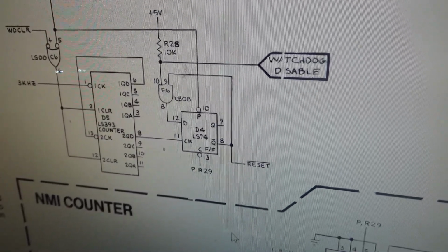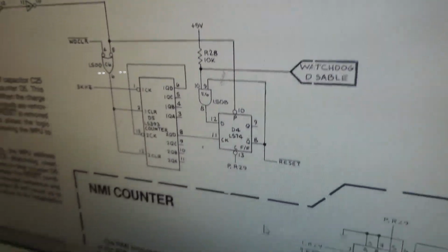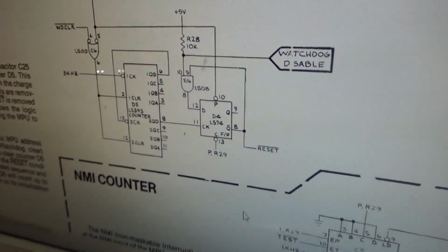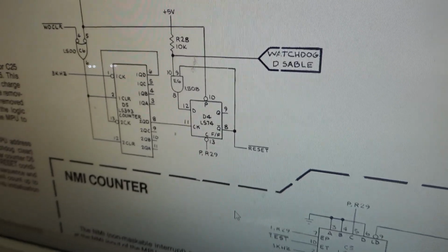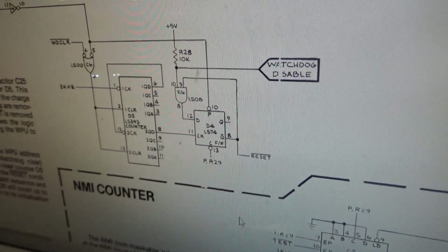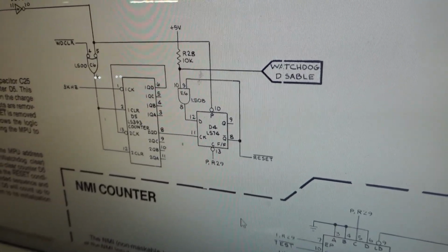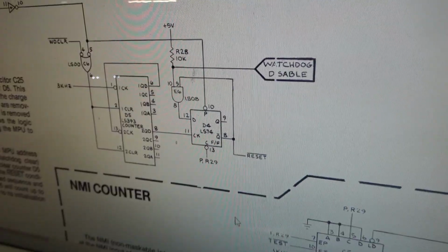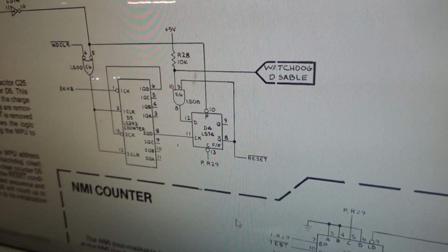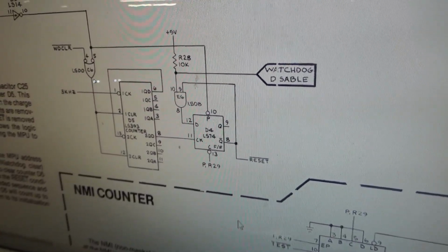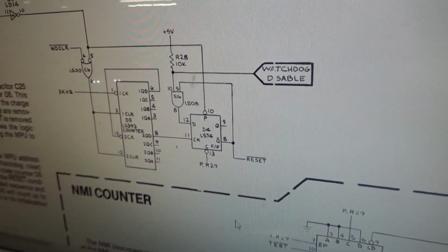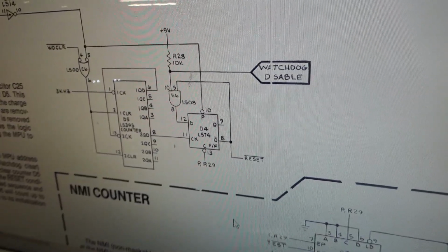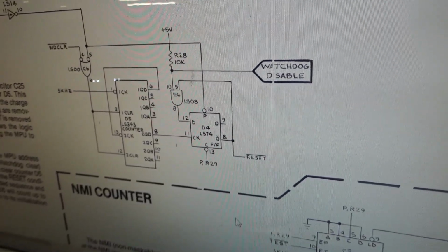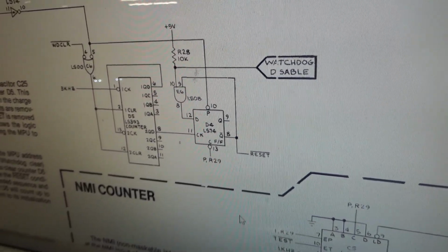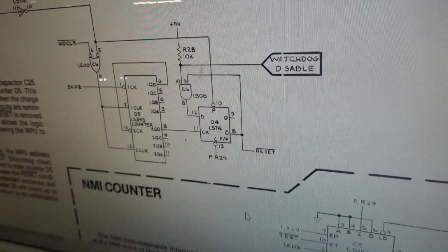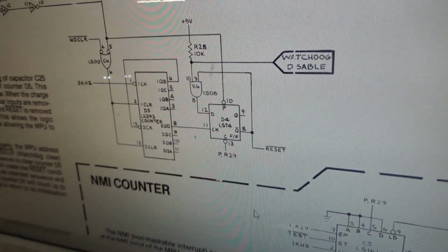If the MPU program is operating properly, the MPU address decoding circuitry will output the watchdog clear signal at predetermined intervals - but it's not operating properly. This serves to clear counter D5 before it counts up to the state that will create the reset condition. If the MPU program strays from its intended sequence and does not output the watchdog clear signal, counter D5 will count up to the reset state and cause the MPU to return to its initialization routine.